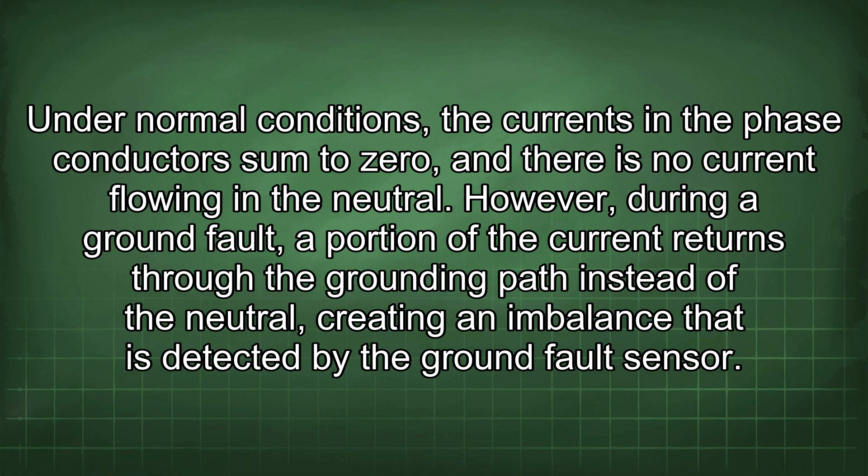Under normal conditions, the currents in the phase conductors sum to zero, and there is no current flowing in the neutral. However, during a ground fault, a portion of the current returns through the grounding path instead of the neutral, creating an imbalance that is detected by the ground fault sensor.